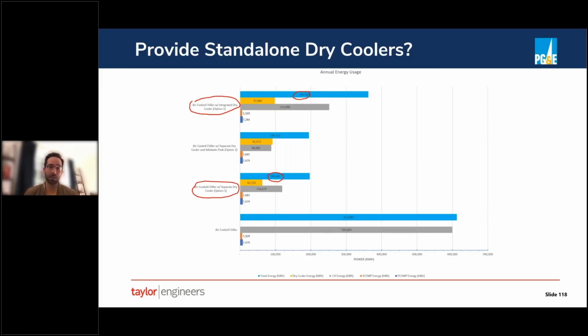But the reason that this was true in our case was that the systems under consideration had very high primary flows. So this was a primary only system, but with very high minimum flows. So it meant that we had a lot of hours where we were diluting the return temperature going to the dry cooler. And the return temperatures coming back from the loads were very high in the system. So they were 90 degrees. And there was a huge free cooling opportunity that we were essentially wrecking by blending in chilled water supply at 60 degrees with 90 degrees coming back from the load.